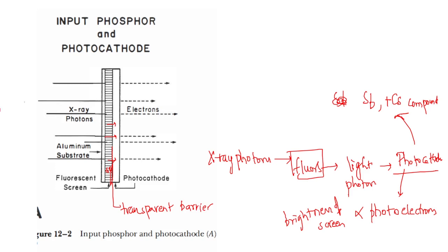To summarize the input side: X-ray photons pass through the aluminum substrate into the fluorescent screen. The fluorescent screen produces light which goes to the photocathode. The photocathode emits electrons. The CsI produces light proportional to the intensity of the X-ray beam, and the photoelectrons emitted are directly proportional to the intensity of that light.